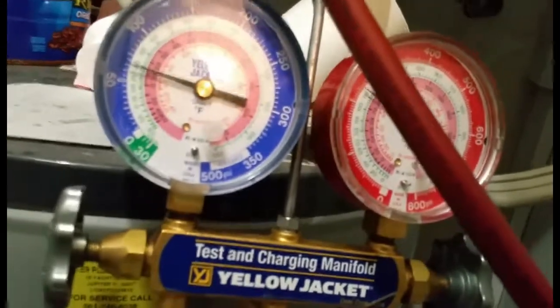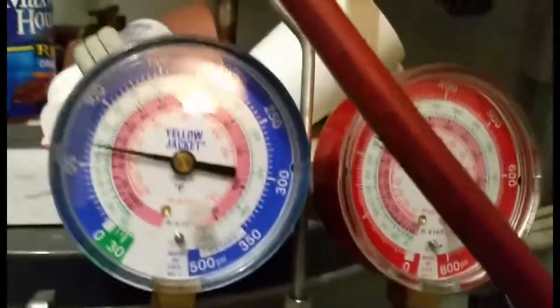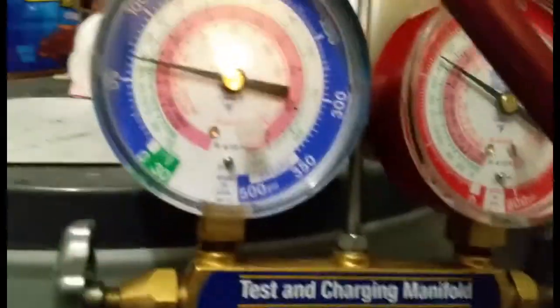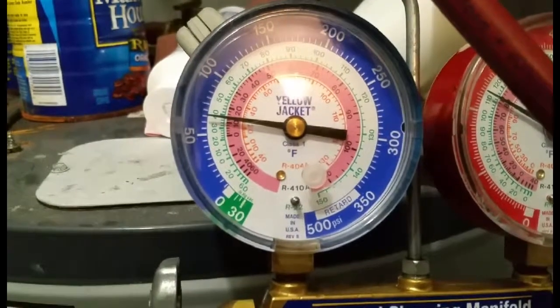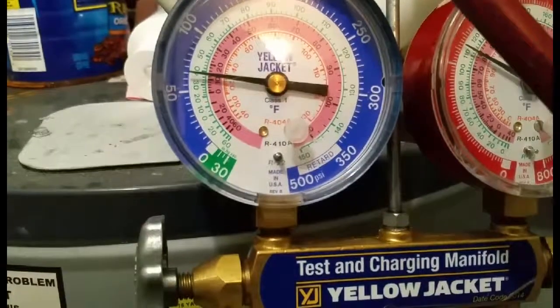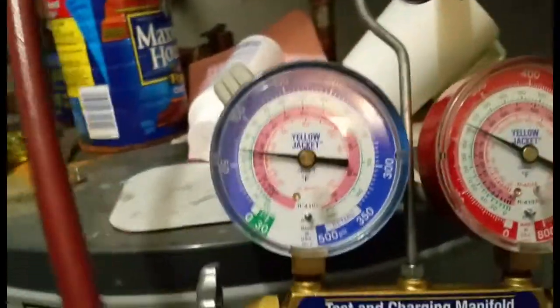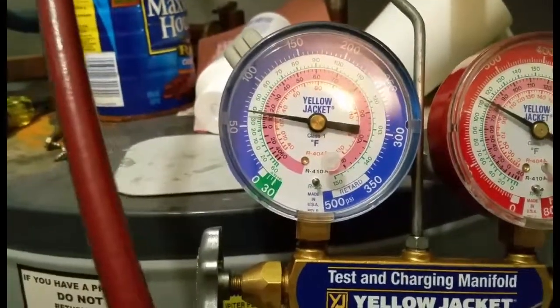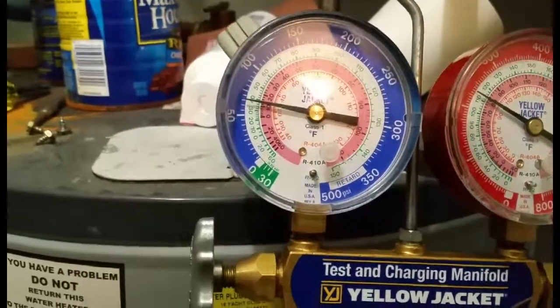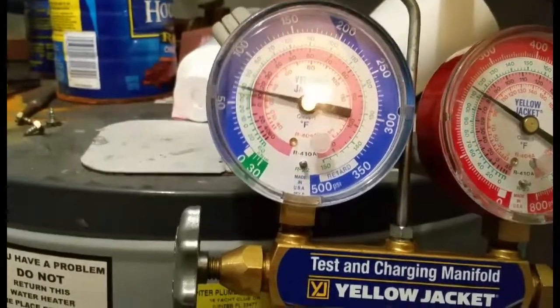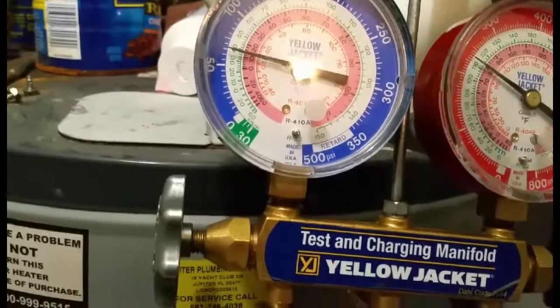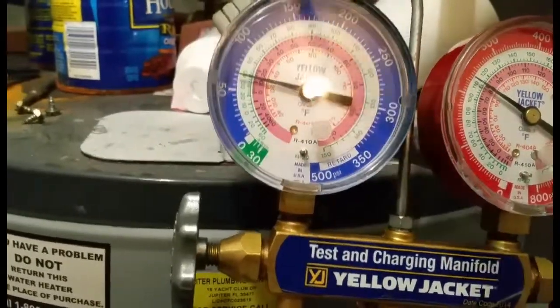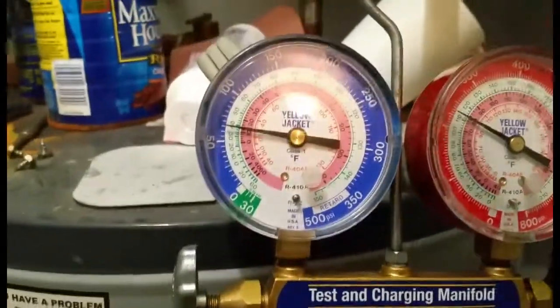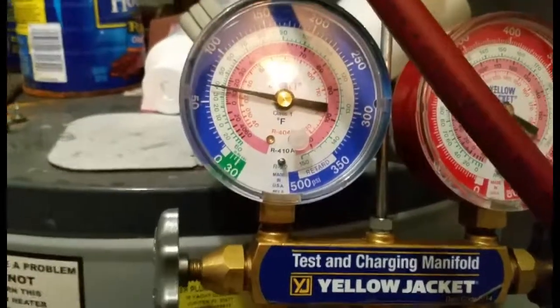With that evap coil dirty the way it is, I would have expected a lower suction. But I guess it's kind of low. I mean, it was 75 degrees when I came in here, I think. No, it was, yeah, 75. But there's no heat load in here neither because it's winter time.